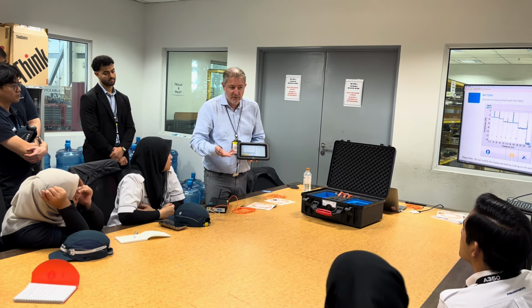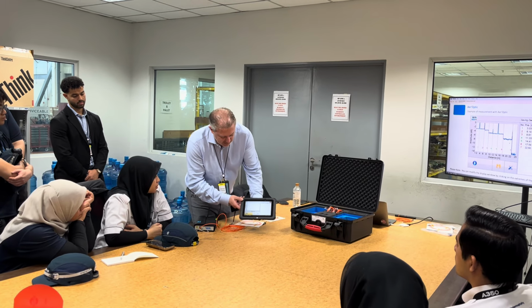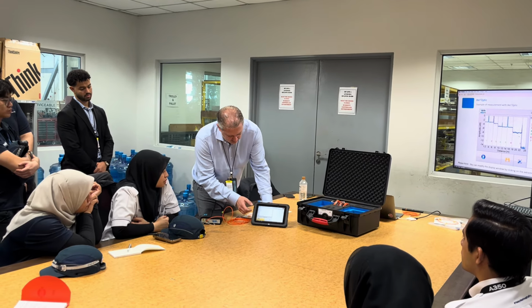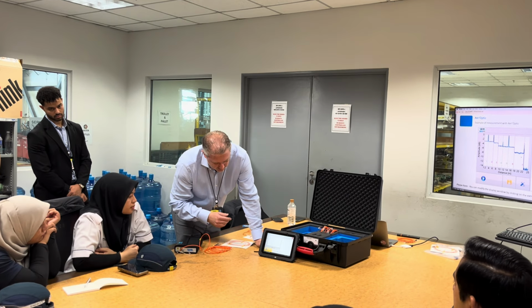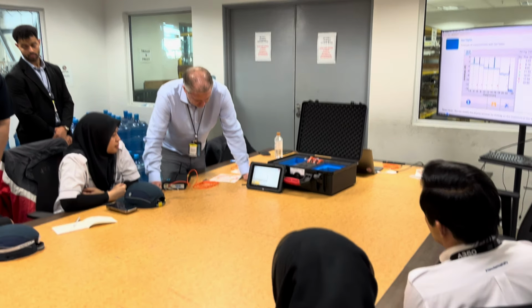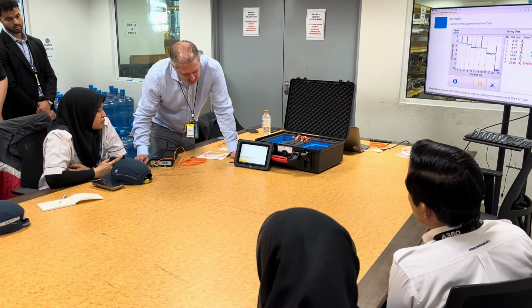So this is when you have to be careful, because now I have a laser that is working over there, and now I have the graph which is going to be drawn. So it's scanning the points one by one. You see some reflectance at the connection point.